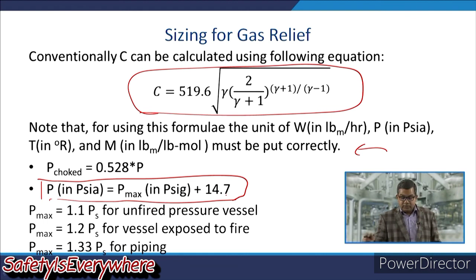So, P choked is equal to 0.528 into P, and P in PSIA is equal to P maximum in PSIG plus 14.7. This type of consistency must always be remembered. P maximum is equal to 1.1 PS for an unfired pressure vessel, P maximum is equal to 1.2 PS for a vessel exposed to fire, and P maximum is equal to 1.33 PS for piping. So, these are the three different scenarios.